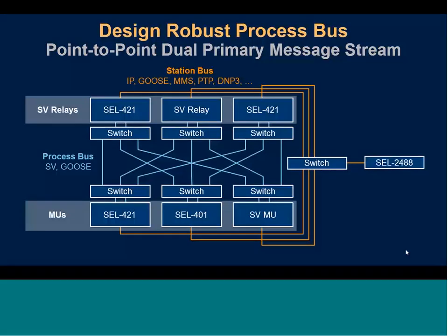The reason for this is to mitigate any sort of failure points. What we can do is use technologies like spanning tree protocol or software-defined networking to reroute traffic in the case of a failed link. For instance, if my primary link between the merging unit and the relay on the left is severed, like in the slide, I can use the other available paths to reroute the data so that I can recover from that.